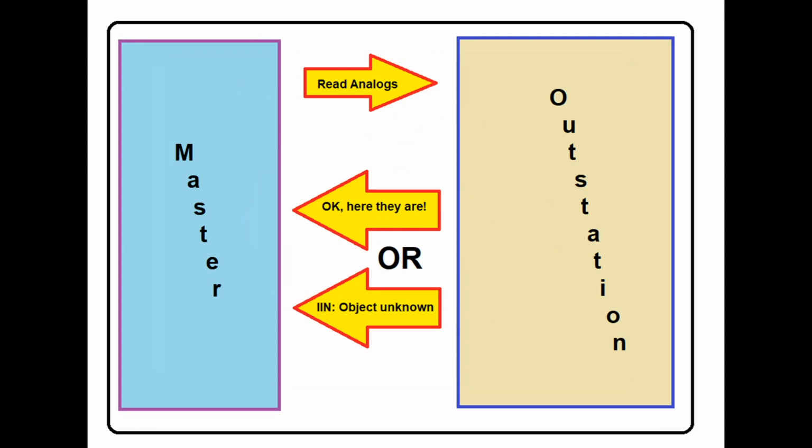When stating a certain subset must support a certain capability, support just means that the outstation understands the request and responds appropriately. While an outstation is required to support requests, it is not required to be configured with all point types admitted to the subset. For example, there is a requirement to support analog inputs. If an outstation has no such points, an appropriate response to a read for analog inputs is one with the object unknown internal indication flag set. It can return the analog inputs if it has any, or it can return the object unknown response if it doesn't.